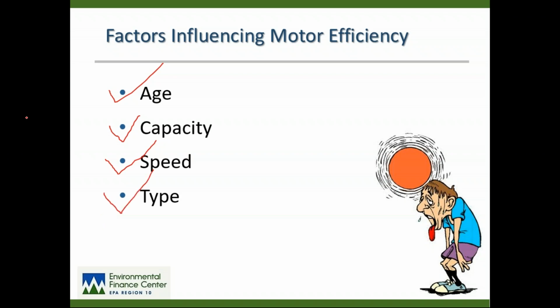The fourth factor is the type of the motor. Most motors in the water business, most motors used in US industry, are what are called induction motors. The very largest motors that are moving water 24 hours a day, 7 days a week over mountain ranges and pushing water many hundreds or thousands of miles are called synchronous motors. And they have a much lower power to weight ratio. They tend to be very heavy, overbuilt, and very expensive. But again, they are slightly more efficient than induction motors. Maybe some of you might have some synchronous motors in your system, especially if you have some very high horsepower motors. The fifth factor is temperature.